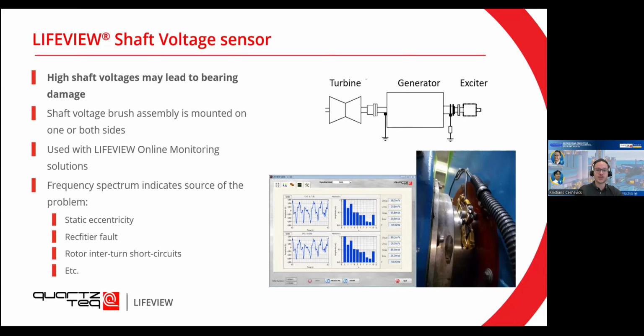So you can do both the shaft measurement, flux measurement, and PD measurement with the same type of device. And finally, those who remember that with the PD part, I was telling you that by looking at the partial discharge pattern, you can actually establish what kind of fault you have. The same thing applies to shaft voltage. So not just by looking at the signal, but by doing a frequency analysis, a harmonic analysis of your signal, you can actually find that, for example, you have a static eccentricity, a rectifier fault, or maybe some rotor interturn shorts. So it gives you, again, another data point so you can plan your outages and your repairs much better.